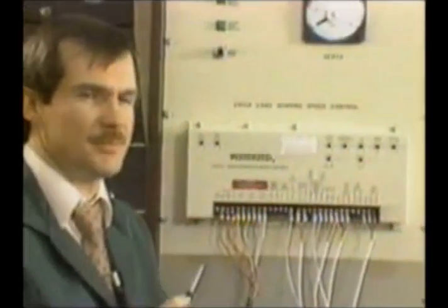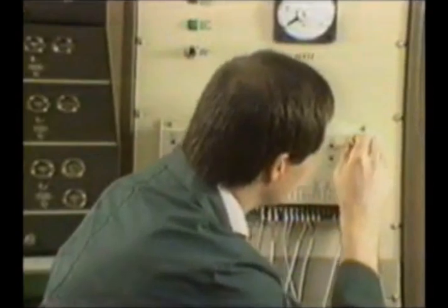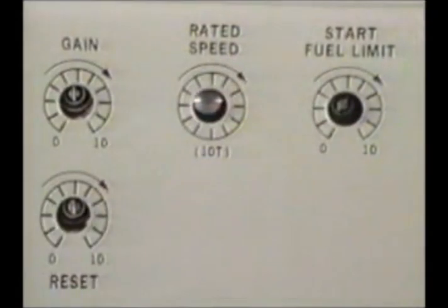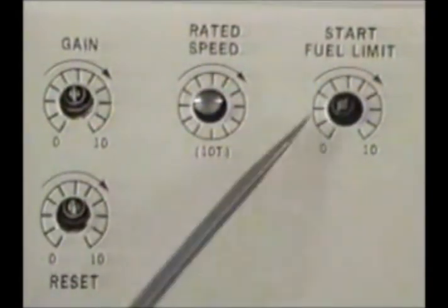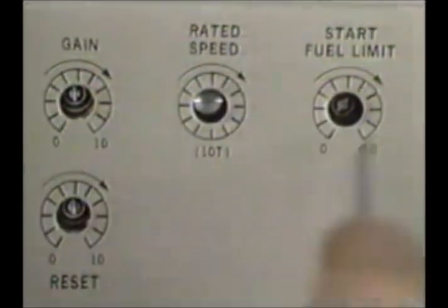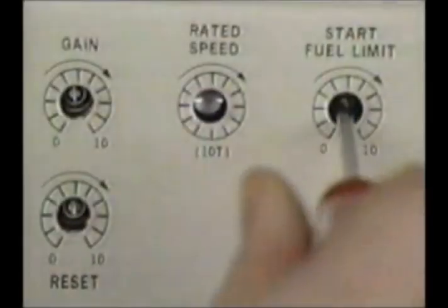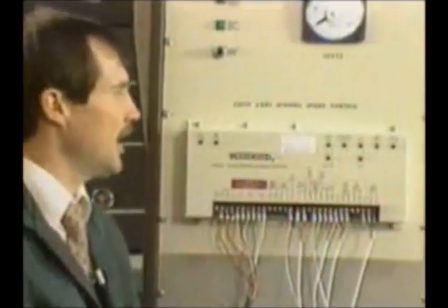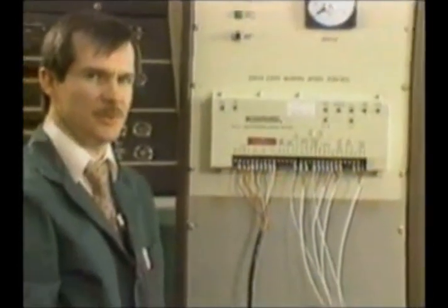Our rated speed potentiometer, now if it's already preset, if you know this is already preset for the speed of your prime mover, do not adjust the rated speed potentiometer. In this case, it is not, so I'm going to turn my rated speed potentiometer fully counterclockwise. This is a 10-turn potentiometer. So let me turn it until I hit a stop going counterclockwise. The start fuel limit potentiometer, I'm going to set up for full clockwise. So now we have preset all the potentiometers on the 2301A control.